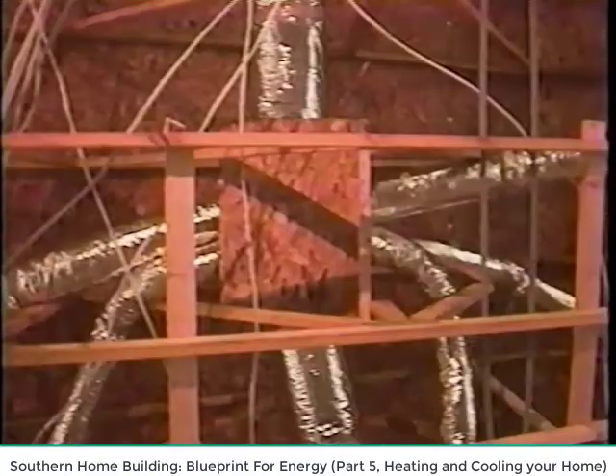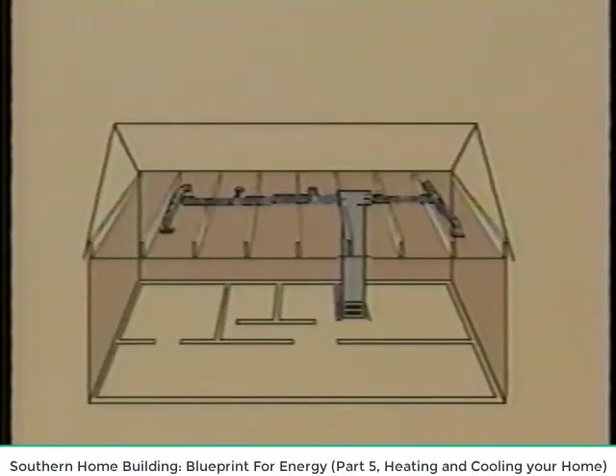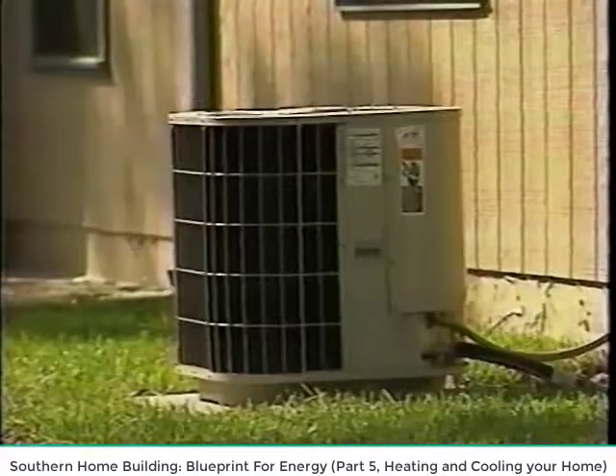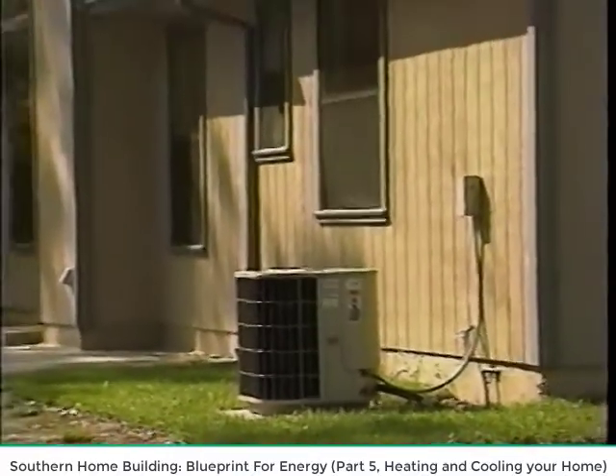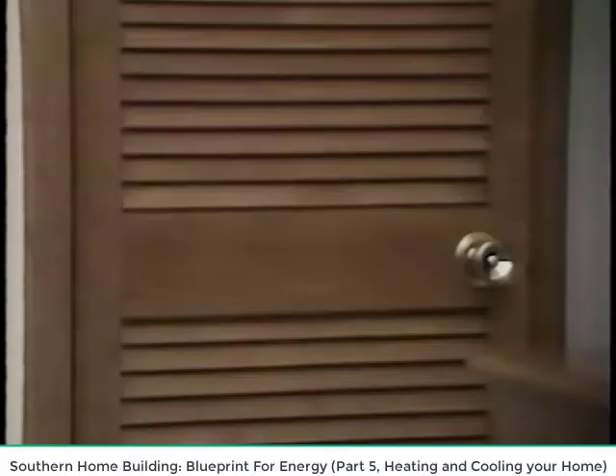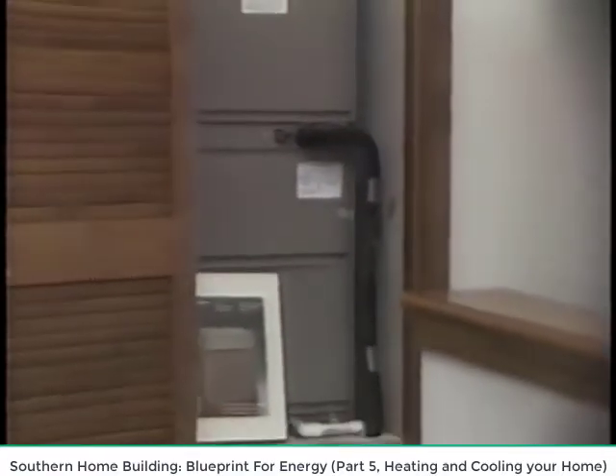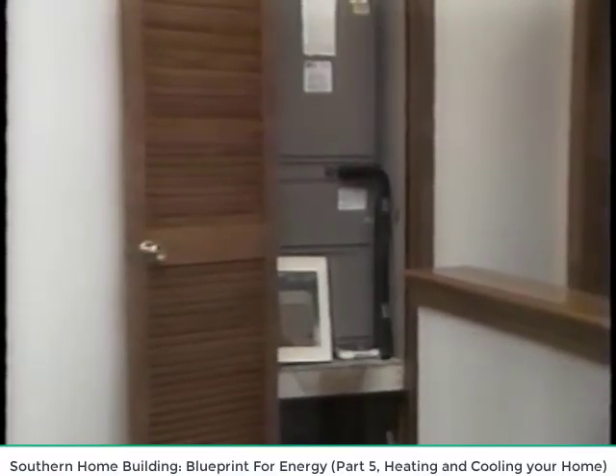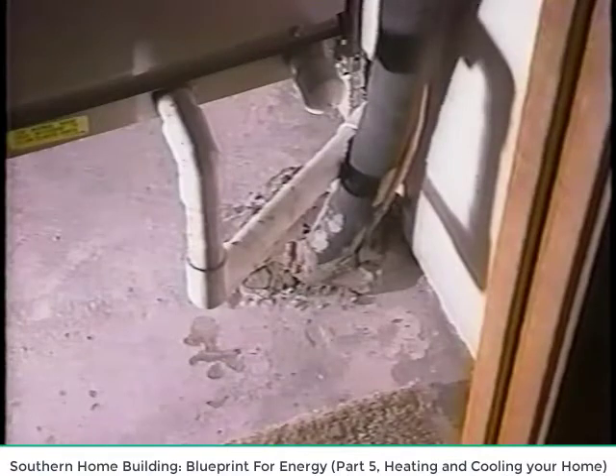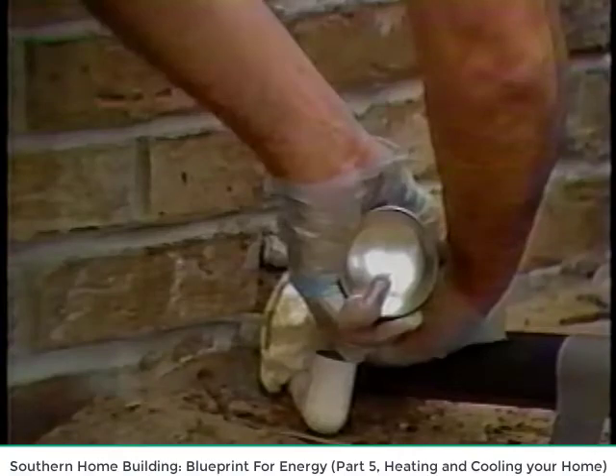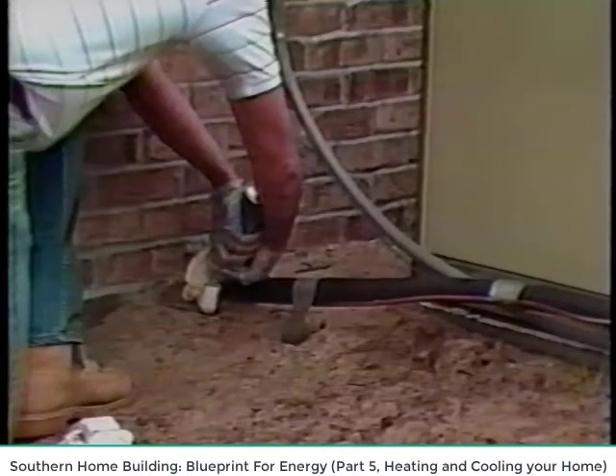In a typical system, an average of 20% of all the air sent into the duct leaks out into the attic where it provides no benefit. A reduction in the amount of duct reduces the wasteful leakage, resulting in lower heating and cooling bills. And the heat pump can be smaller at a savings of hundreds of dollars. Remember, the most cost-effective and energy-efficient location for the air handler is within the conditioned space. However, when the air handler is located inside, the pipe for the refrigerant lines needs to be sealed at the inside opening as well as at the outside opening to prevent air from leaking into the house.